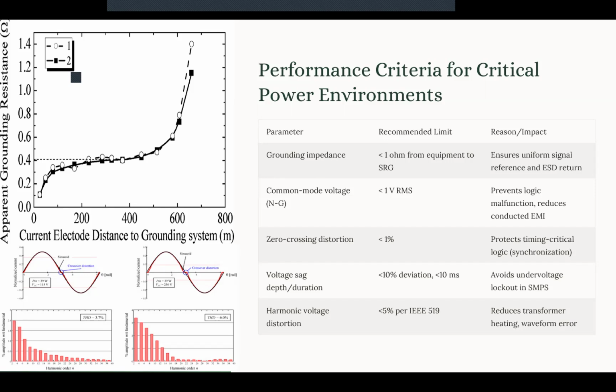Let's talk about it. This zero crossing distortion is the distortion of the AC waveform when the AC waveform crosses the zero value, the zero point, in the time varying behavior that it has. This is very critical for the timing in logic circuits, like those circuits in switch mode power supplies that rely on an accurate zero crossing detection. And if we don't meet these criteria, it would end up in a misfiring of the power electronic devices, leading to some lockup or erratic voltage regulation or increased harmonic generation because of the improper firing angles.